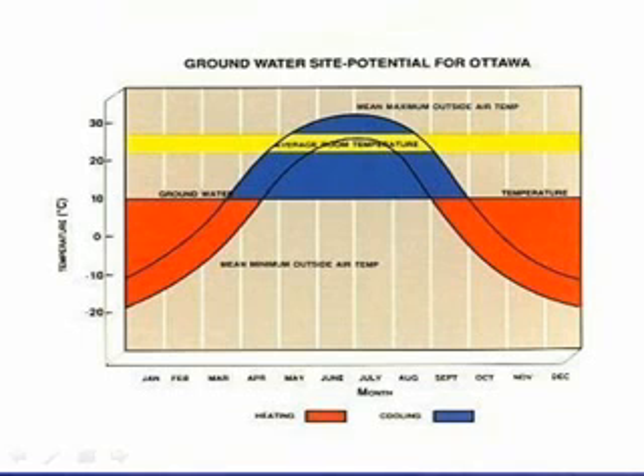So in the wintertime, it's cold. We'll say it averages between minus 10, minus 20. Obviously, you're going to have those minus 30, minus 40 degree days, and you might have the 0 degree day. But it's going to average down in the range between these two lines. Down here, your air temperature is less than the groundwater temperature, which I'll say for Ottawa is 10 degrees centigrade. So if the air temperature during the winter is lower than the groundwater temperature, you should be able to take heat out of the groundwater and heat up the air in your building.